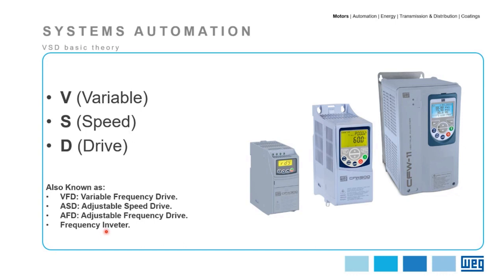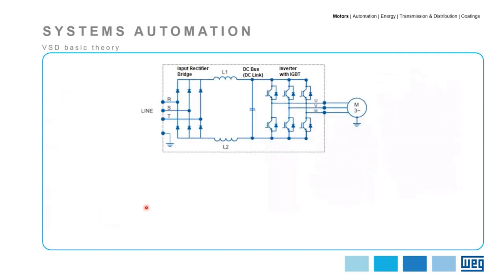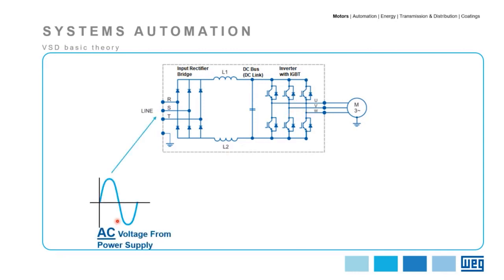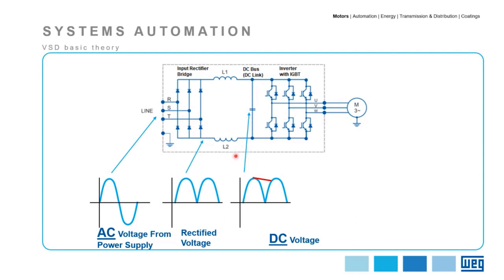The construction of a typical low voltage six-pulse VSD can be divided into three main parts: the input rectifier bridge, the DC bus or DC link, and the inverter unit. The AC input voltage passes through the rectifier unit, producing a DC voltage. However, this DC voltage has ripples, and therefore the capacitors from the DC link smooth out these ripples. As a consequence, a clean DC voltage is available to the inverter section.